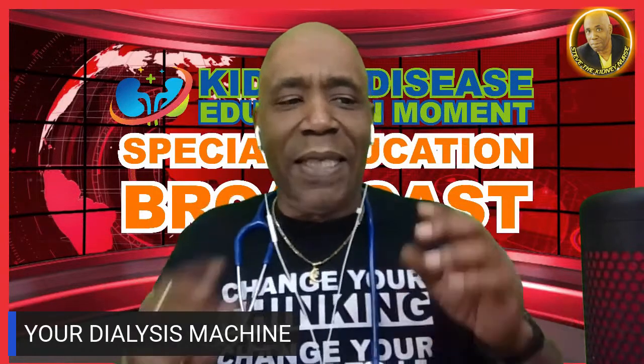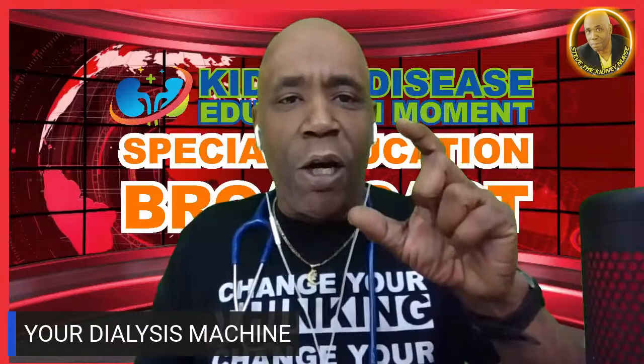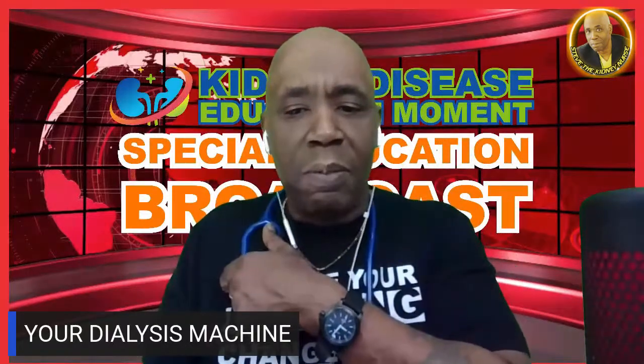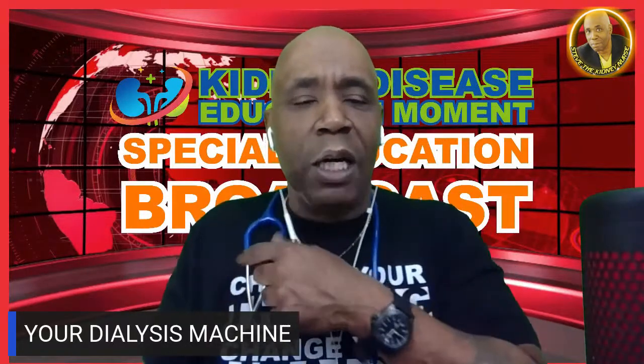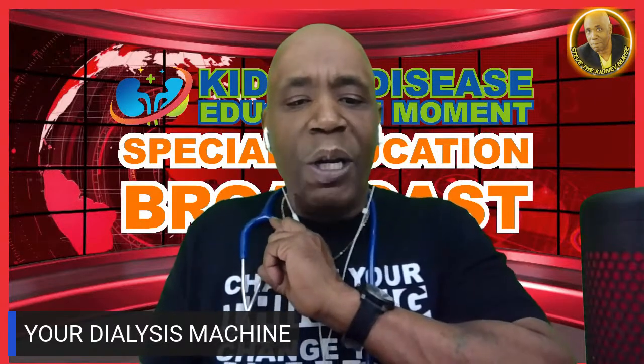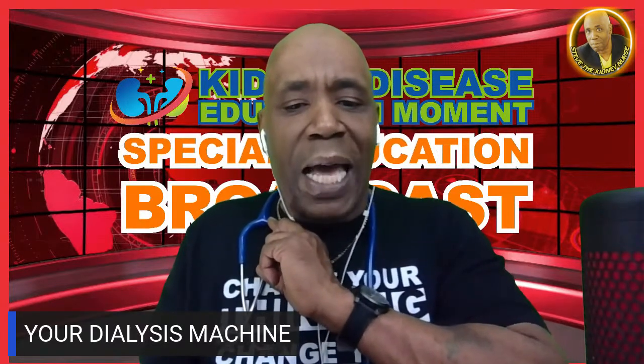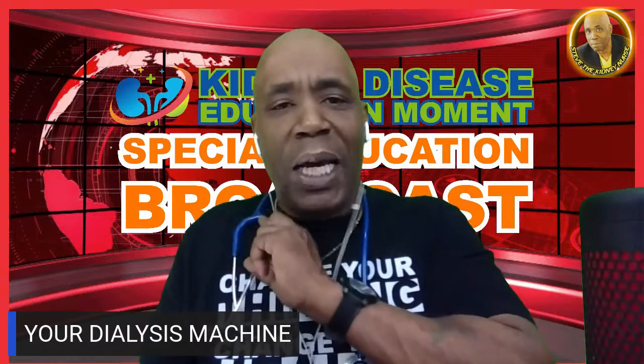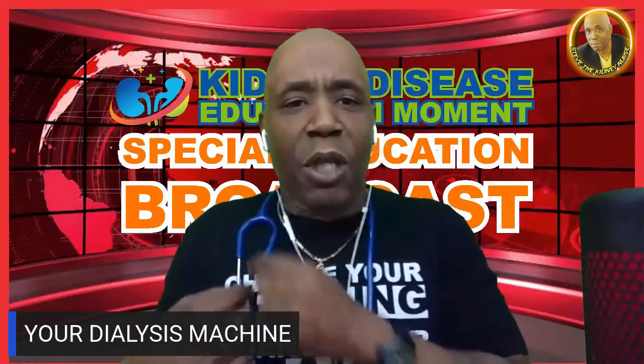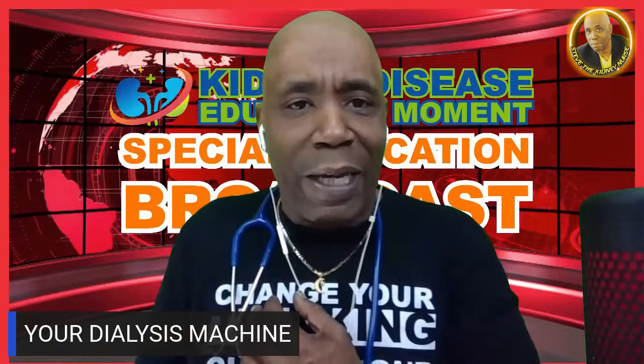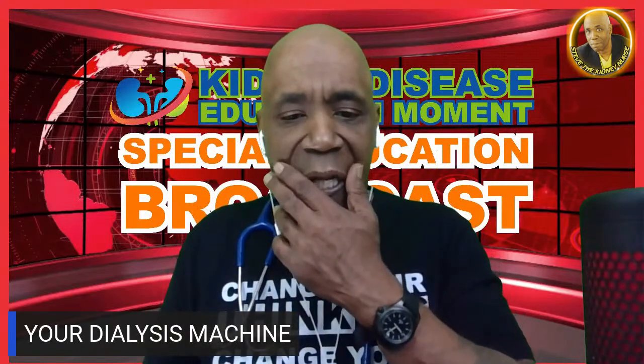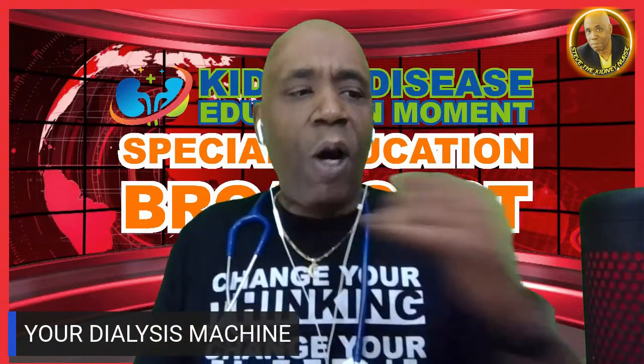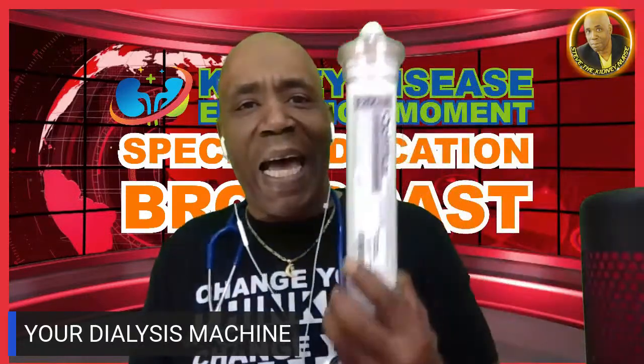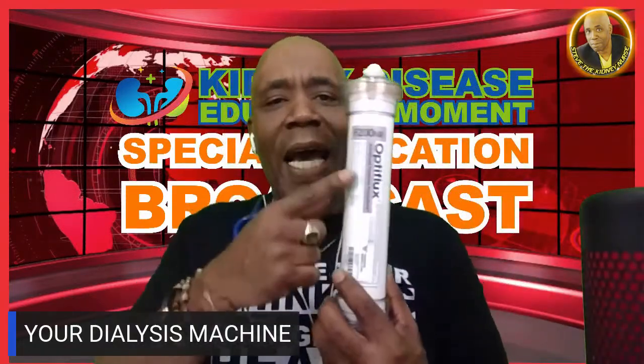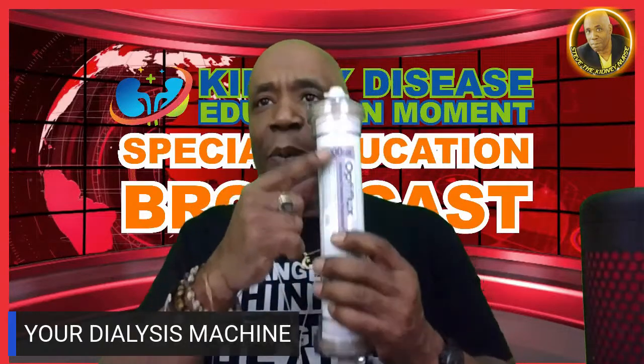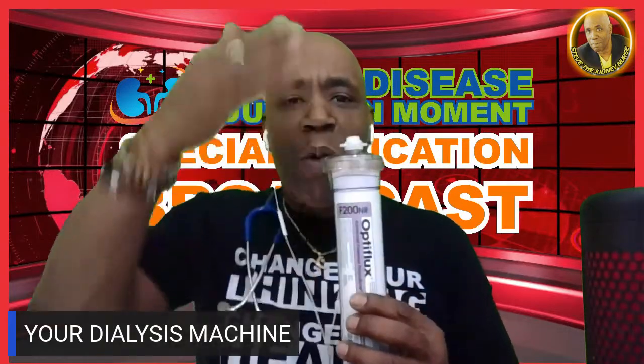And in some places, they have this thing called a hemosafe clamp. It's a clip that connects on the venous CVC bloodline and to the bloodline. This white clamp, so the lines don't separate. Also, you're supposed to check the position of the dialyzer. You see how this is? This is the right side is supposed to be up, with this number facing up.